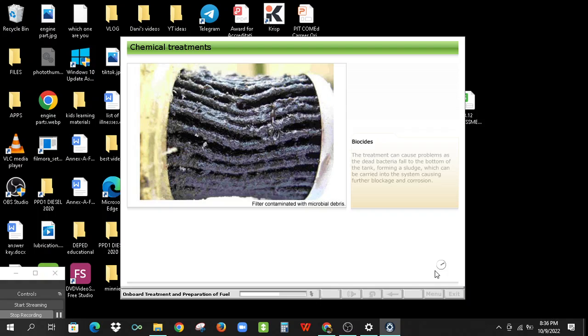The treatment can cause problems as the dead bacteria fall to the bottom of the tank, forming a sludge which can be carried into the system, causing further blockage and corrosion. To prevent recurrence of microbes, it is necessary to completely sterilize the system, including all tanks, pipework and fittings. As this is not usually possible on an operational ship, it is best to avoid the problem altogether. Keep checking for water in those fuel tanks.